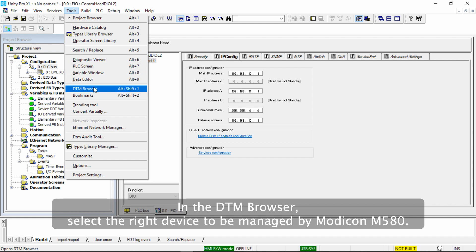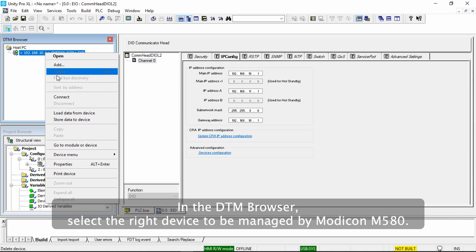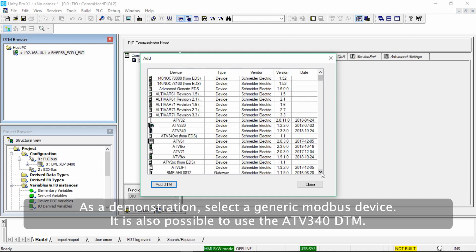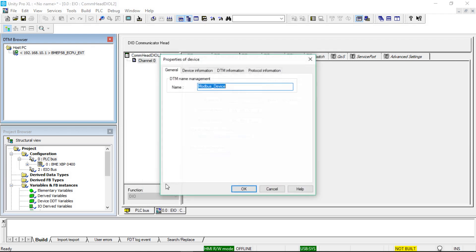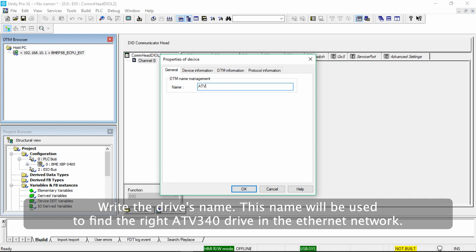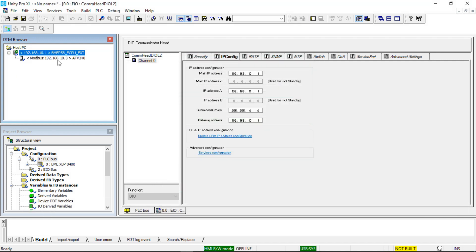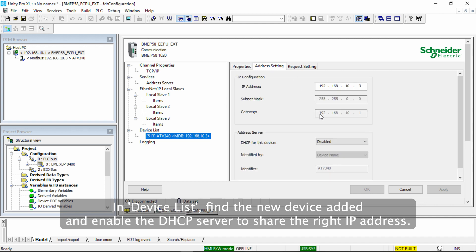In the DTM browser, select the right device to be managed by Modicon M580. As a demonstration, select a generic Modbus device. It is also possible to use the ATV340 DTM. Write the drive's name — this name will be used to find the right ATV340 drive in the Ethernet network. In Device List, find the new device added and enable the DHCP server to share the right IP address.